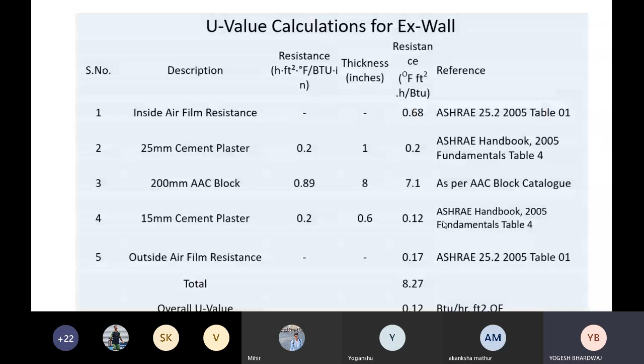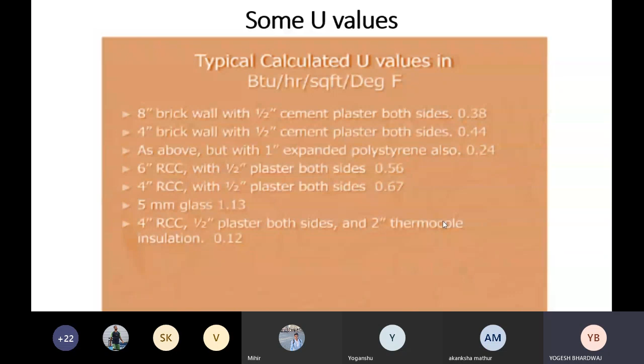These are some U values you can see on your screen. For an 8-inch brick wall with half-inch cement plaster on both sides, the U value is 0.38. For a 4-inch brick wall with half-inch cement plaster on both sides, it is 0.44. Similarly, for a 6-inch RCC roof with half-inch plaster on both sides, it is 0.56. These are the typical U values for different kinds of building constructions.